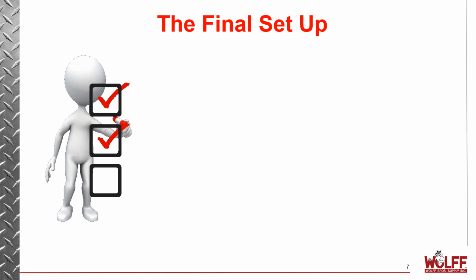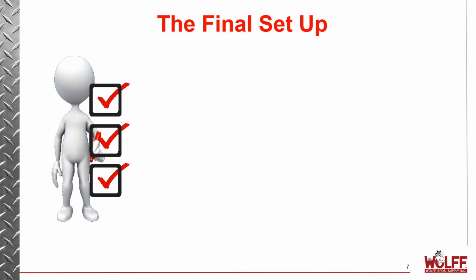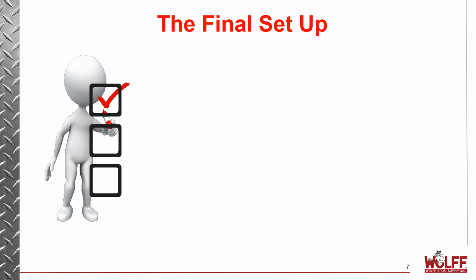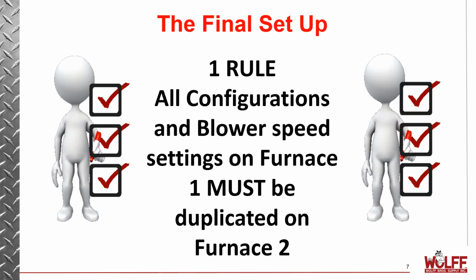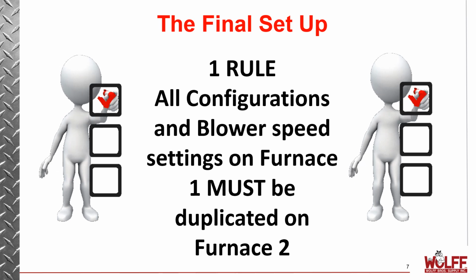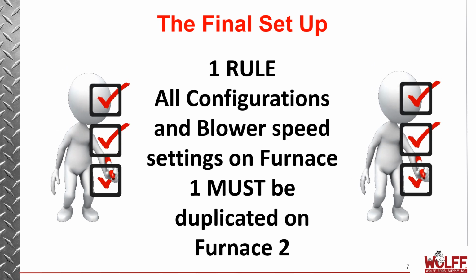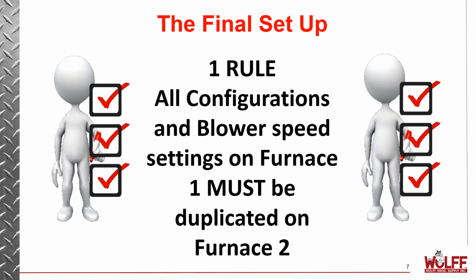So now we're at the final setup or configuration of the unit. There's basically only one rule to follow, and that rule is that for all configurations and blower speed settings on furnace 1, you must duplicate them on furnace 2.